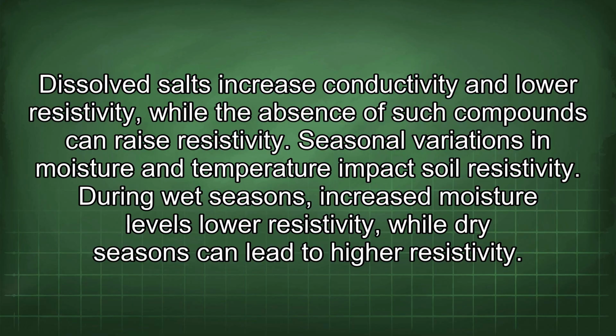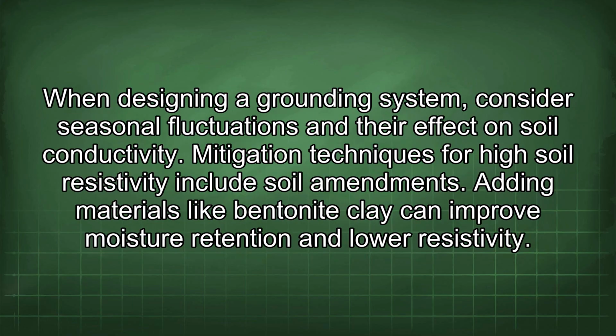Seasonal variations in moisture and temperature impact soil resistivity. During wet seasons, increased moisture levels lower resistivity, while dry seasons can lead to higher resistivity. When designing a grounding system, consider seasonal fluctuations and their effect on soil conductivity. Mitigation techniques for high soil resistivity include soil amendments. Adding materials like bentonite clay can improve moisture retention and lower resistivity.